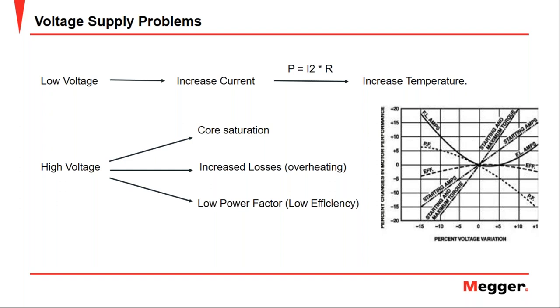What happens if we have problems in the power supply, in the voltage supply? Here we can observe the consequences in the motor when it works with over or low voltage. Think about it: a steady state, three-phase system. There can be only three things that are wrong with your voltage condition. First, the level. Second, the balance. And third, the distortion. Typically, you will have a combo of those with different grades of severity. Very important to have in mind.